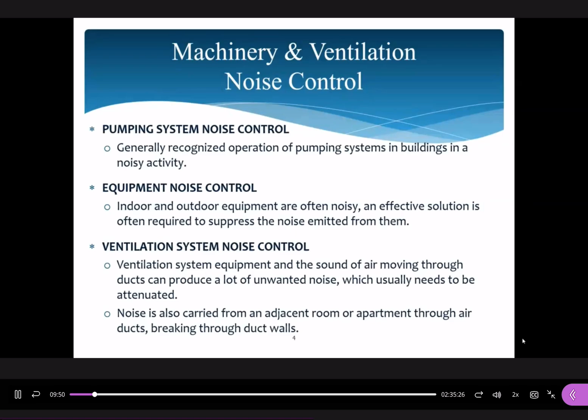Regarding positions of equipment, we could put it inside an enclosure or small plant room, with fitted walls or greater distance from the receiver. The receiver refers to any building—such as when we put equipment on rooftops, we want to minimize the sound effects reaching adjacent buildings, which are the noise sensitive receivers.